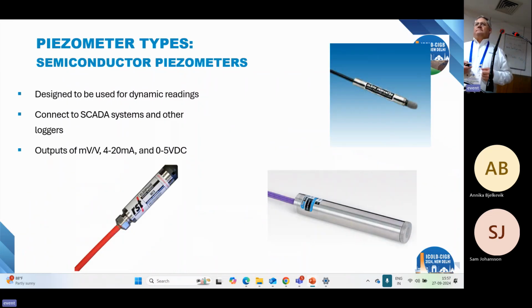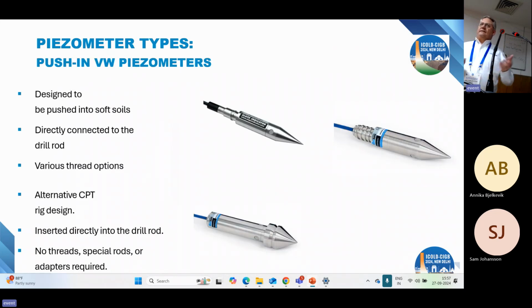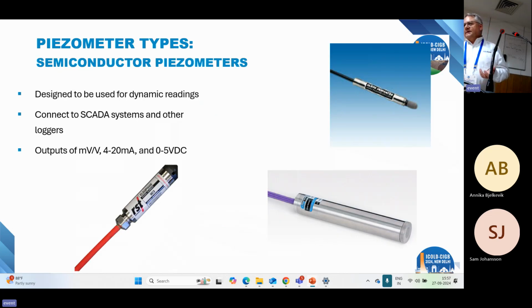There are also semiconductor piezometers. These previously, I guess I'm getting ahead of myself here. They're all vibrating wire style instruments. If you're not familiar with that, it puts out a frequency. There are systems where you want to use semiconductor, maybe because you have an existing system on site to monitor with. It's a SCADA system, or it only reads an analog output type signal. So these can work for 4 to 20 milliamp, millivolt per volt, or 0 to 5 volt DC, and they can be packaged in different ranges as well.